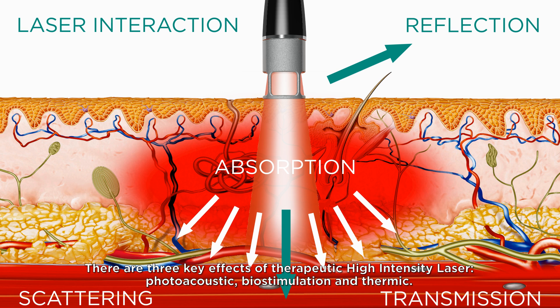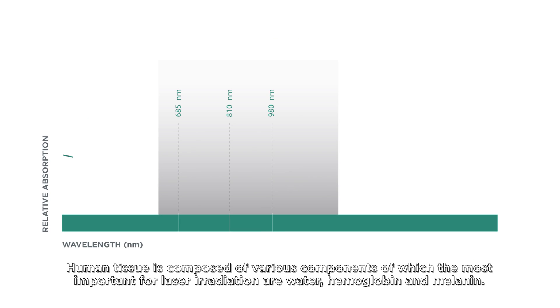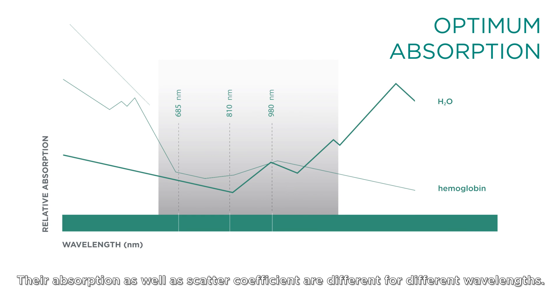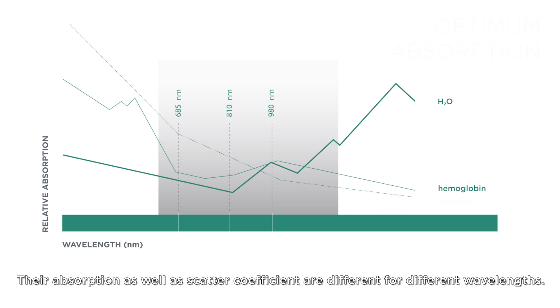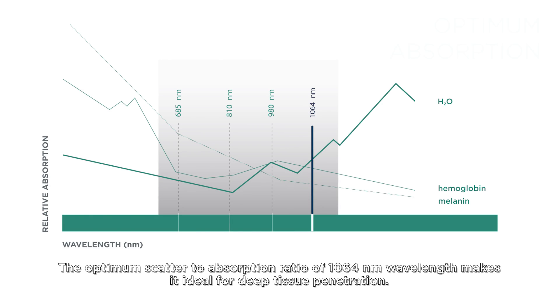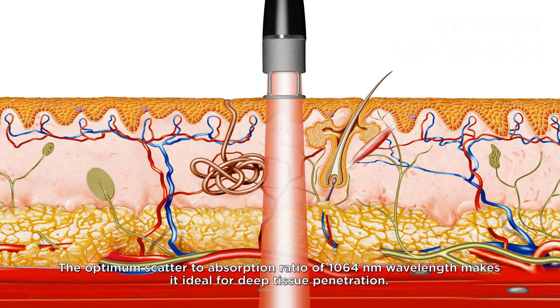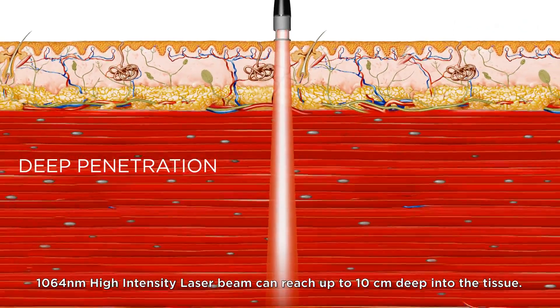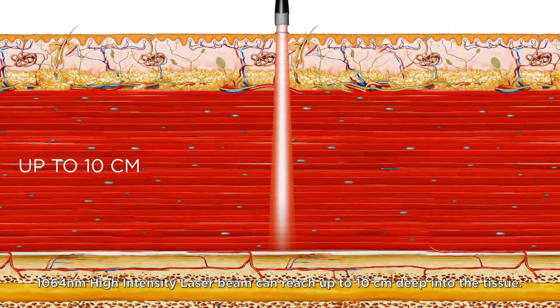There are three key effects of therapeutic high-intensity laser: photoacoustic, biostimulation and thermic. Human tissue is composed of various components, of which the most important for laser irradiation are water, hemoglobin and melanin. Their absorption, as well as the scatter coefficient, are different for different wavelengths. The optimum scatter to absorption ratio of the 1064 nanometer wavelength makes it ideal for deep tissue penetration, and a 1064 nanometer high-intensity laser beam can reach up to 10 centimeters deep into the tissue.